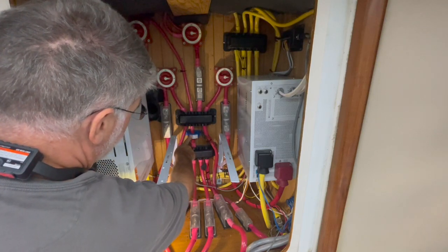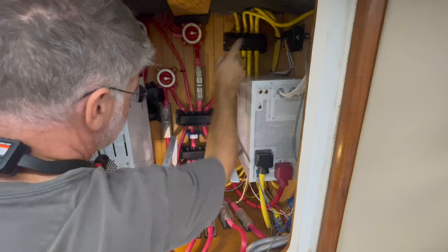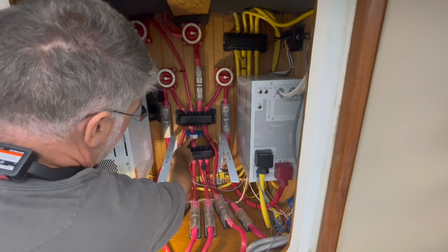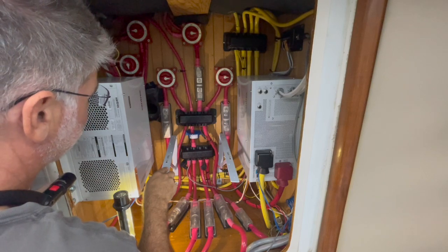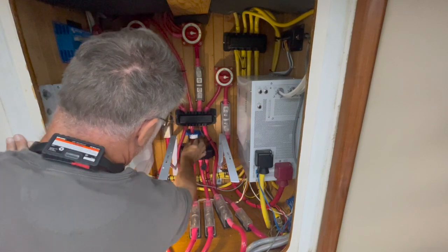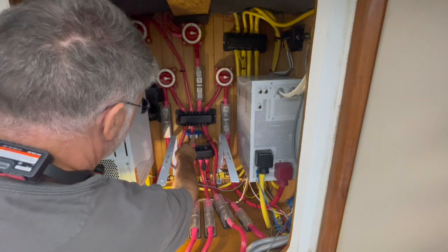This Hall effect sensor and the Maretron box that interprets the information from this Hall effect sensor is not calibrated correctly. I have a shunt that I can measure that data with as well, and they don't agree. I put a clamp meter on here to see if it agreed with this Hall effect sensor, and it did not.